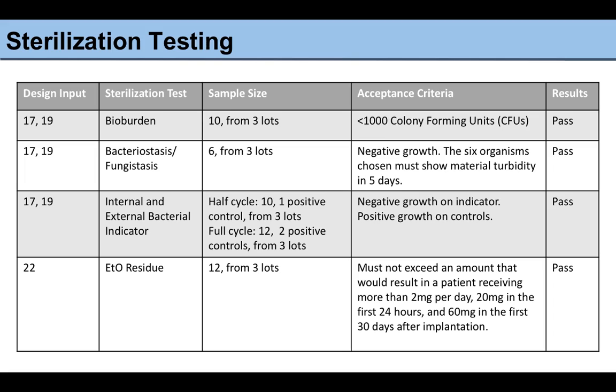For this test to pass, there had to be negative growth on the indicator for both the half and full cycle tests, as well as positive growth on the controls, again to confirm that it was a valid test, and this test passed. Finally, we tested the ETO residue left on our device after sterilization, with a sample size of 12 each from 3 production lots.